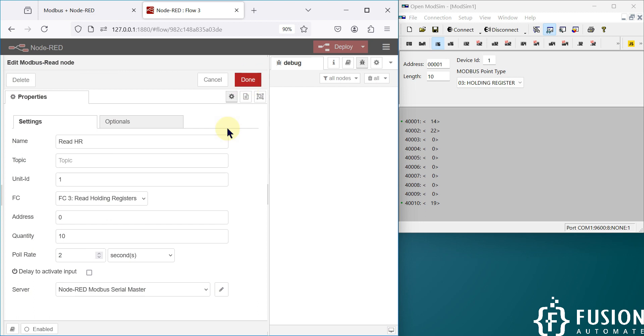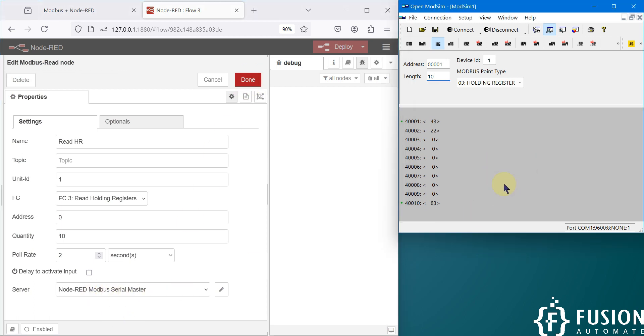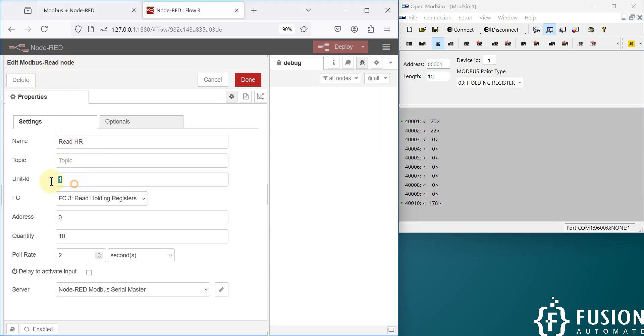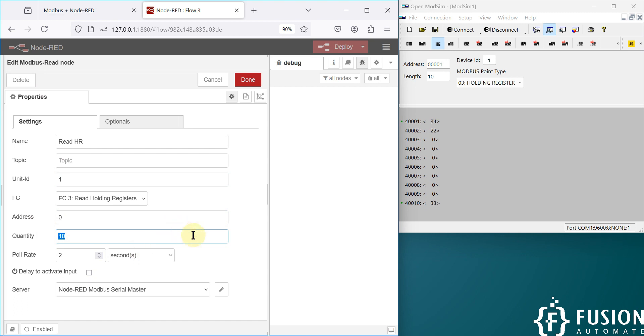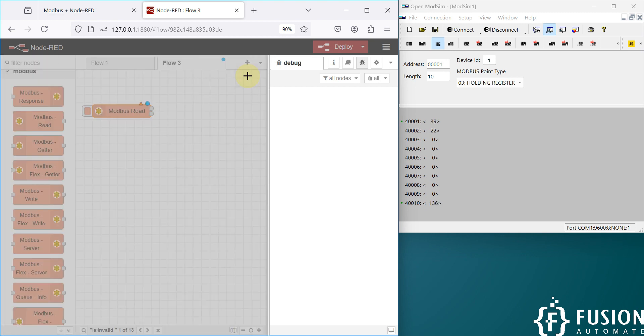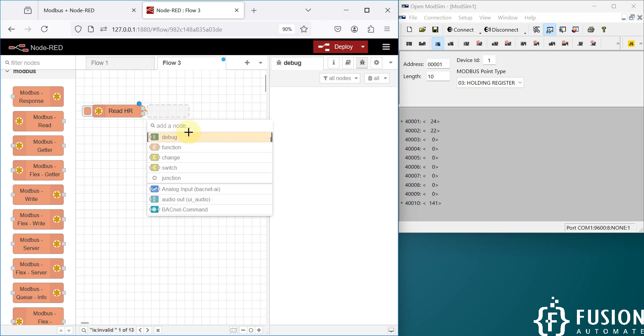We can add it and use it here to read data from the Modbus serial device. So the configuration for the Modbus Read node is: unit ID 1, holding register, starting address 0, quantity 10, poll rate 2 seconds. Press Done, and then add the debug node.